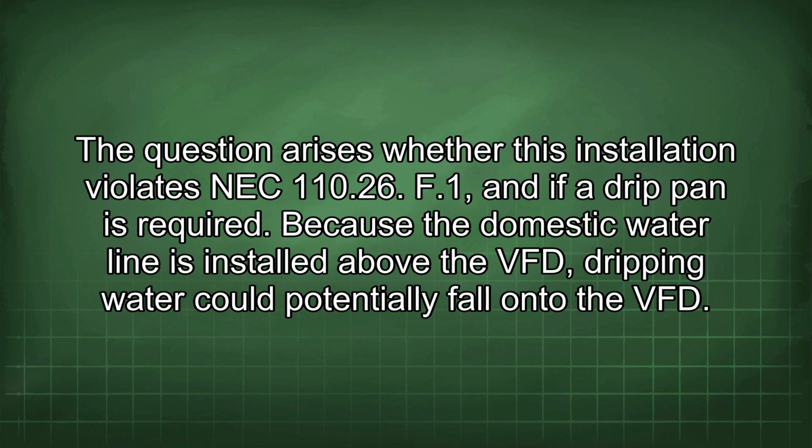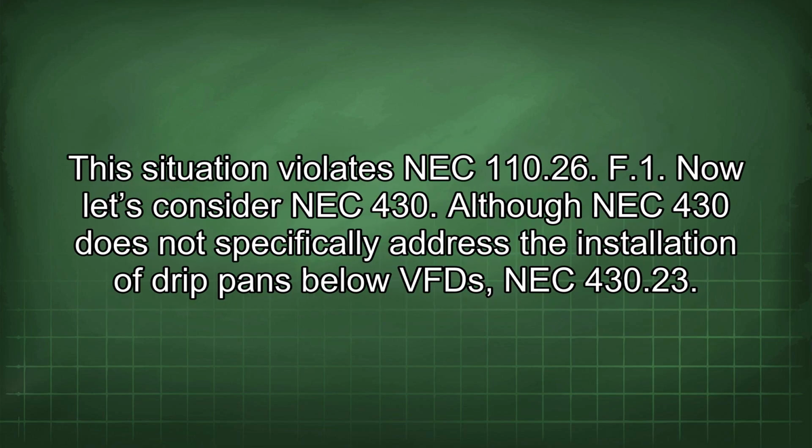Because the domestic water line is installed above the VFD, dripping water could potentially fall onto the VFD. This situation violates NEC 110.26(F)(1). Now let's consider NEC 430.